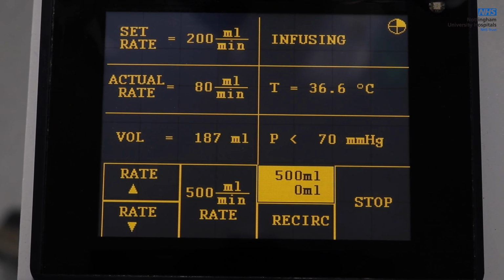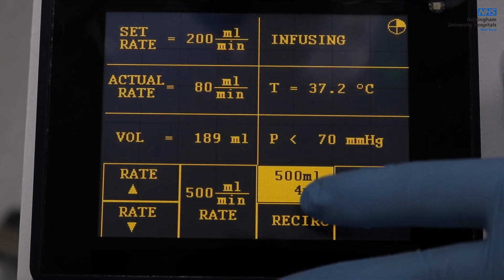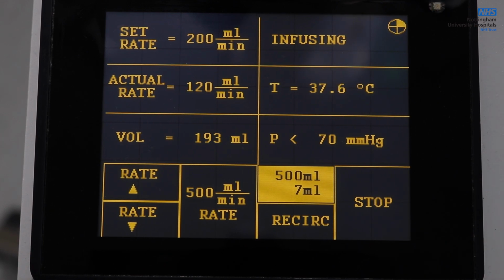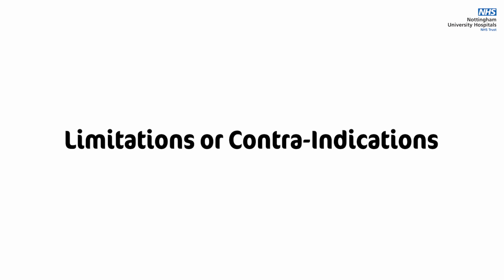Available bolus options are 100 ml, 200 ml, 400 ml, 500 ml, and 1000 ml. Limitations or contraindications which may affect safe use of the device. This device should only be used by staff who have been trained and assessed as competent as per the NUH Medical Devices Training Policy. Do not add solutions containing calcium or other additives that would compromise the anticoagulants in blood products. Clots in blood products may block the flow of fluid and cause overheating.